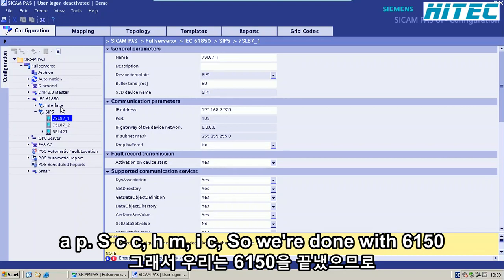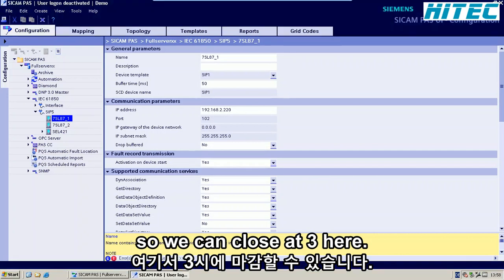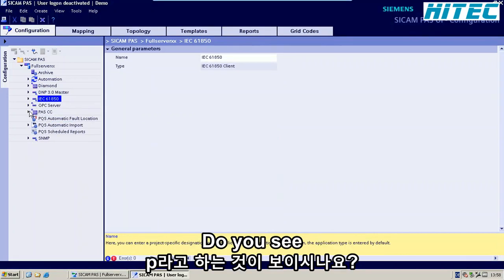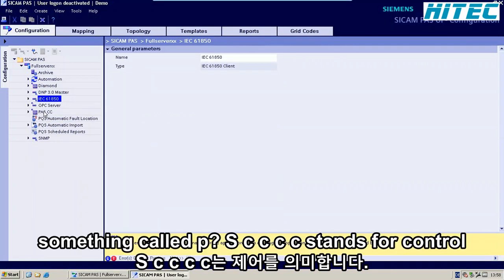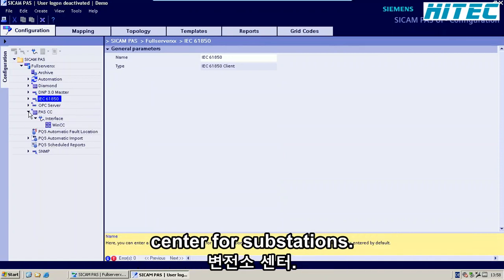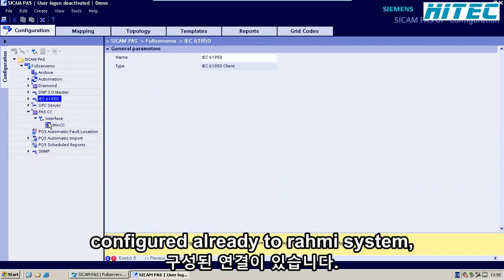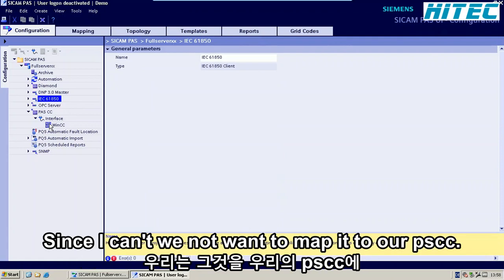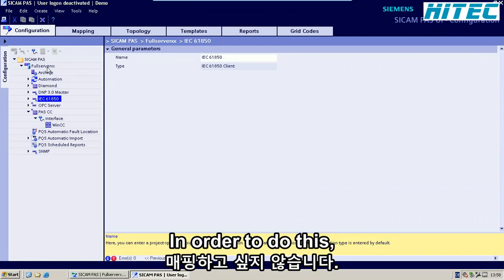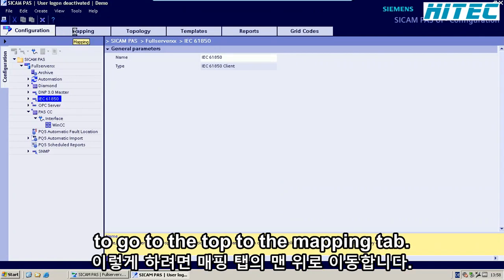So we're done with 61850, so we can close the tree here. And here you see something called PSCC — CC stands for Control Center for Substations. If you open up the tree, you see there's a connection configured already to our HMI system. But now all the information is in SICAM and we want to map it to our PSCC. In order to do this, you go to the top to the Mapping tab.